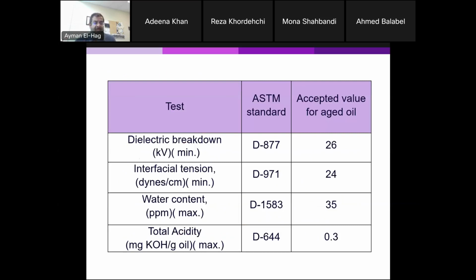For example, for dielectric breakdown, the minimum value is 26 kV. That is the minimum voltage. Now, remember this 26 kV applies when you have a 2.5 millimeter gap between the two electrodes. For new oil, basically this goes to 60 kV. The interfacial tension minimum value is 24. For new oil, it goes, I think, to more than 40. Okay, so that is the accepted value for aged oil.